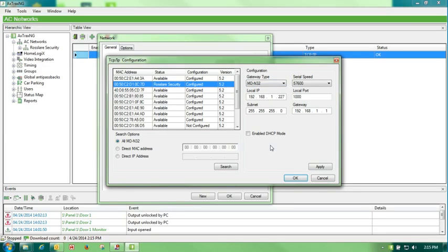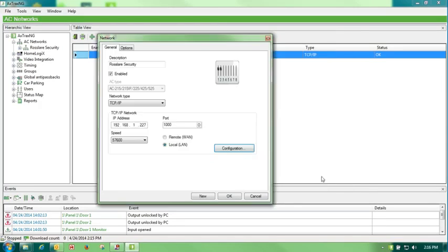Another thing that you always can make sure of is that on your panel itself, on the bottom right hand side, you have an RS-232 to 485 switch. Most often we will need to be on the 485. So double check if you are using a network connection or if you are using an MD14U cable to connect. It always should be to the right on the RS-485.